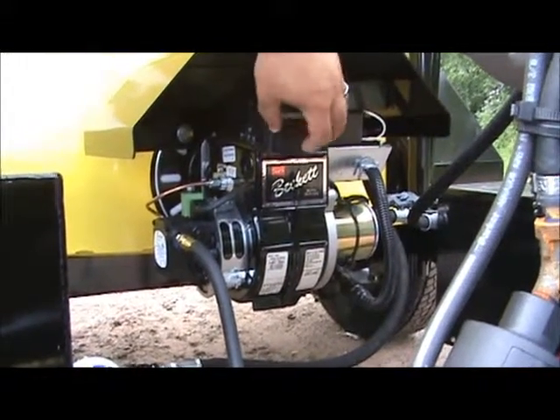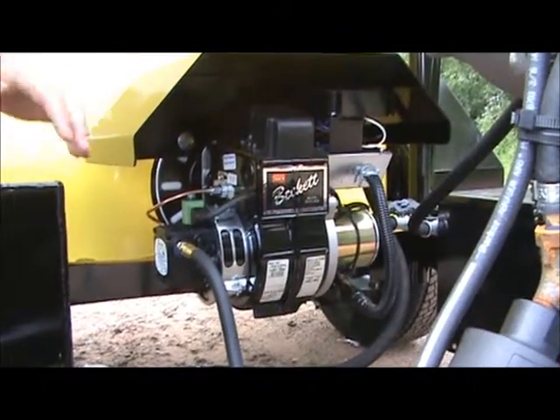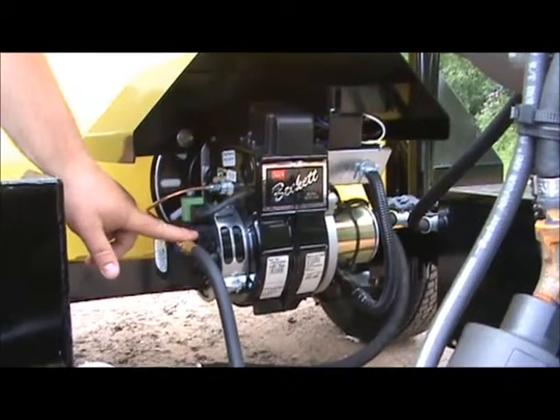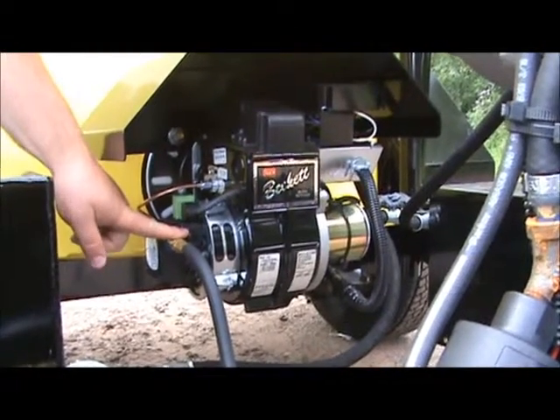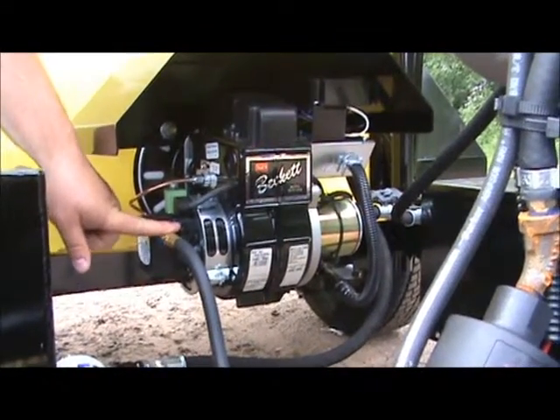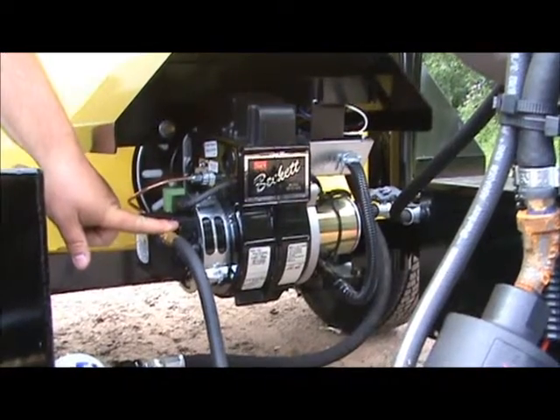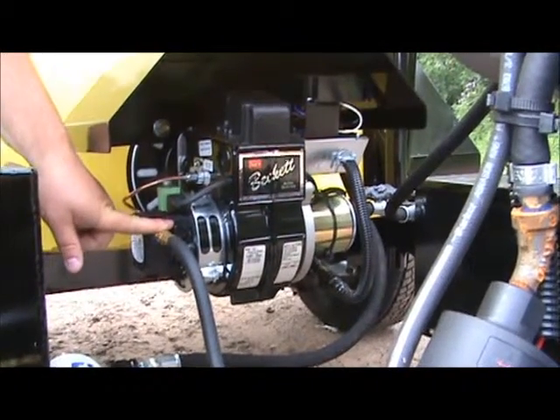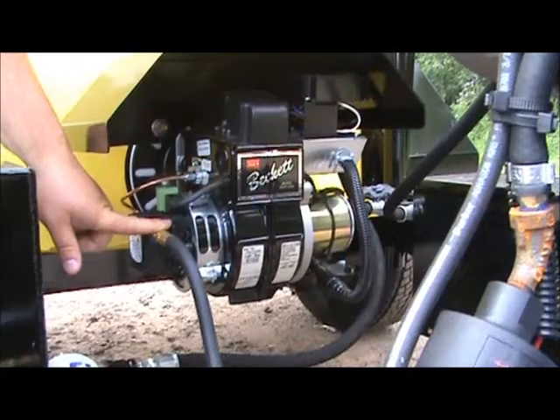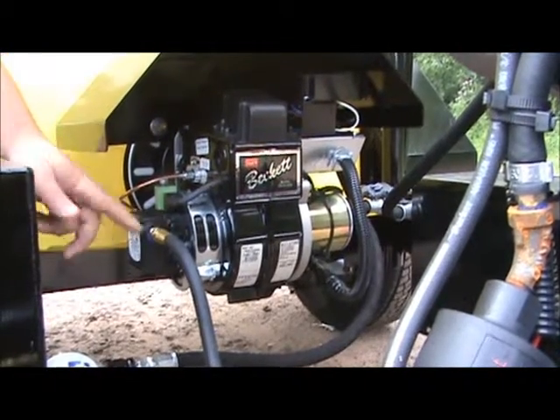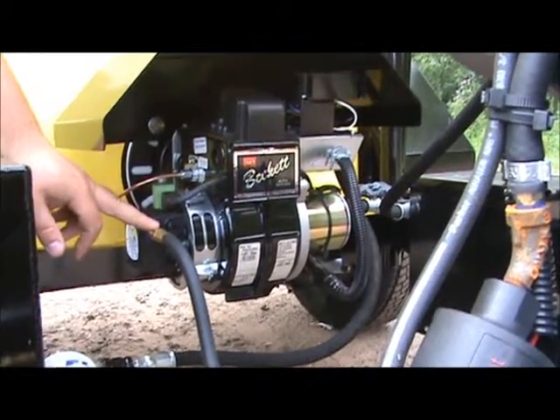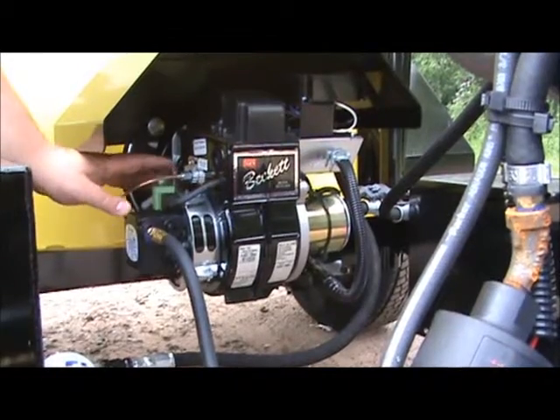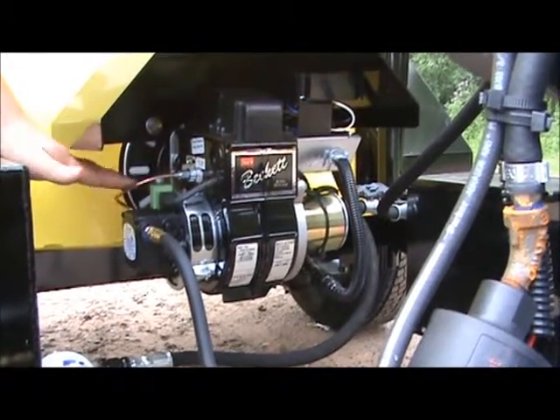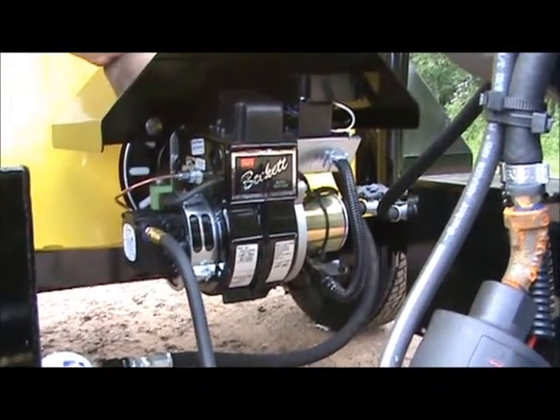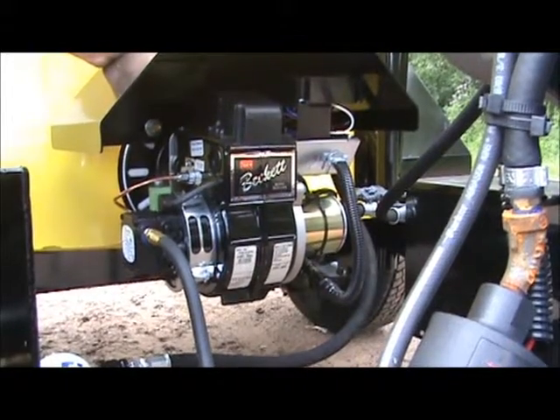The photo eye is on top of this cover. You do have an adjustment for fuel pressure. You shouldn't need to adjust your pressure, but if you ever do, for some reason, if you buy a new fuel pump or whatever, you'll turn it clockwise to turn the pressure up and counterclockwise to turn the pressure down. Now, to adjust the pressure, we suggest that you put a fuel gauge in the system to do that. This burner is designed to run between 100 and 140 psi.